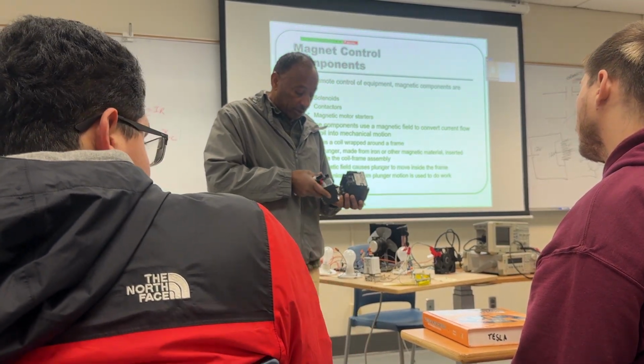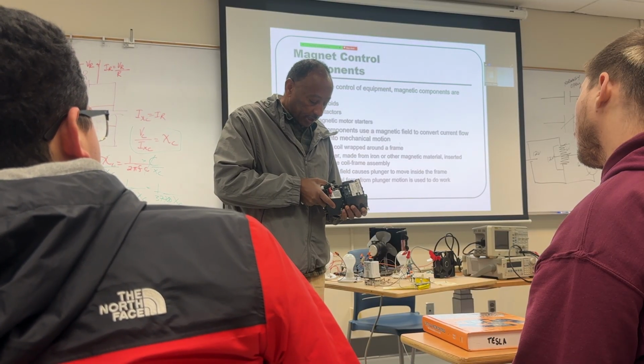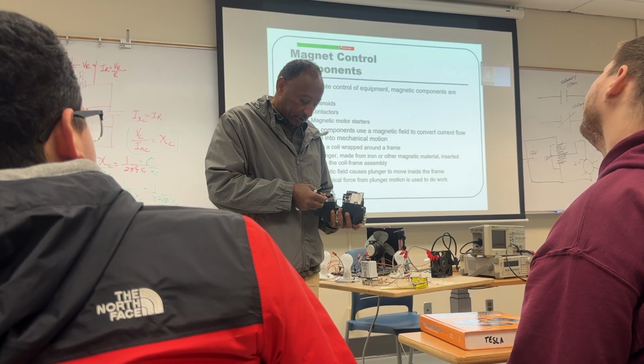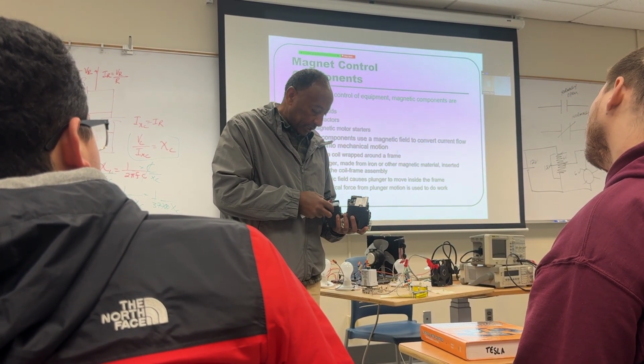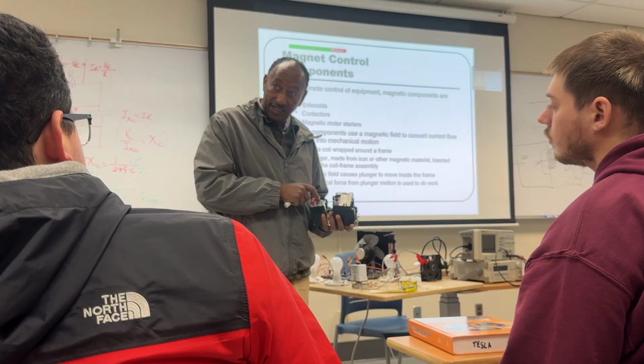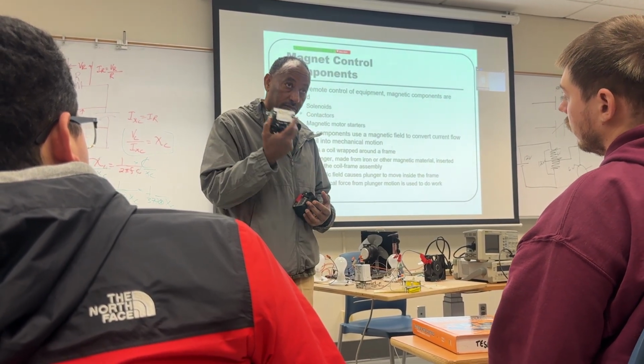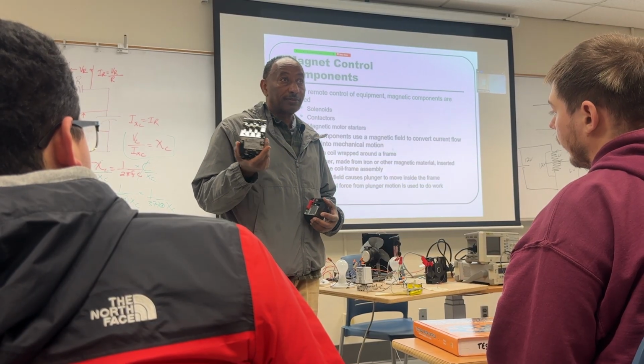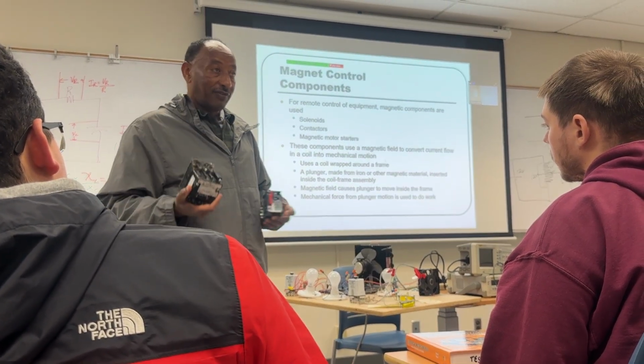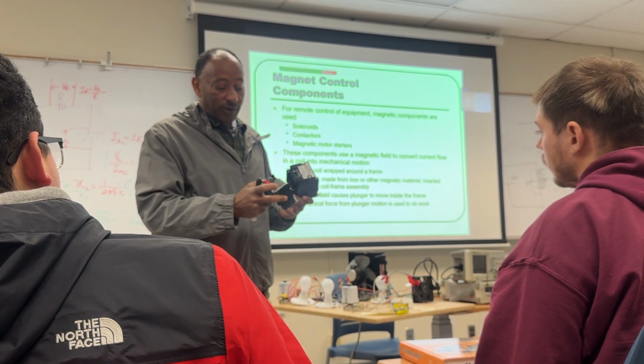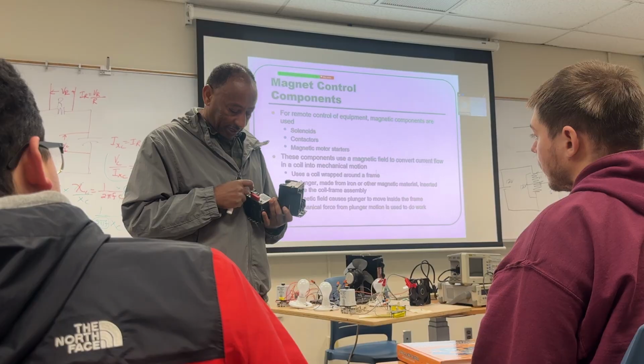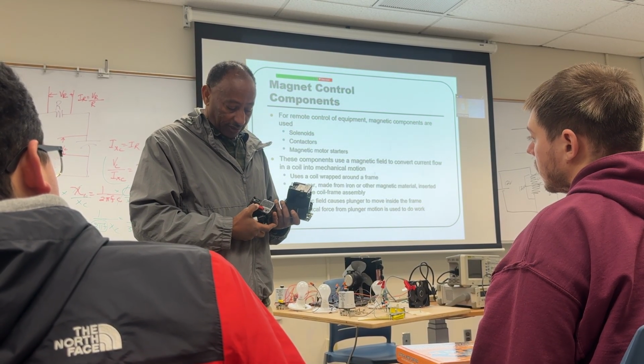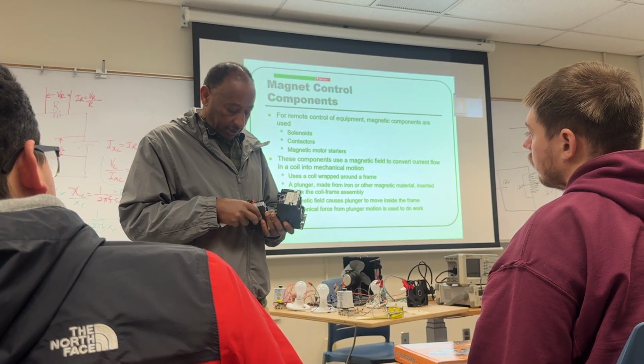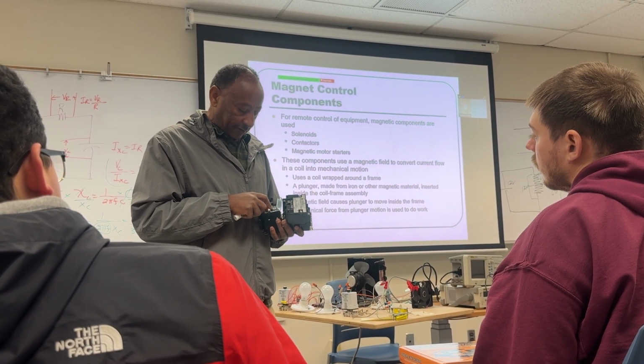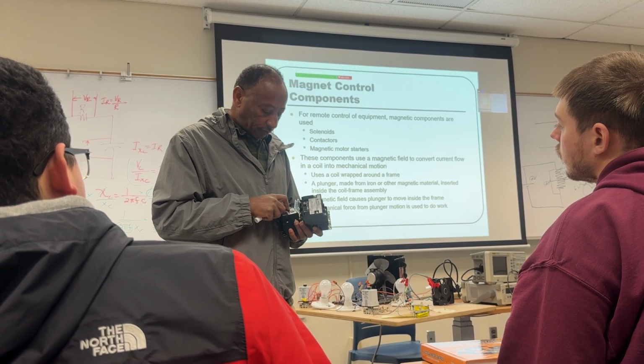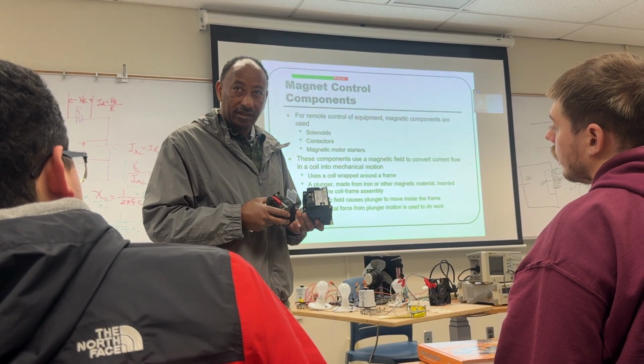In addition to that, it also has other features. This is overcurrent protection. It's a circuit breaker? This is also overload protection. If I'm using a heater or something other than a motor, I just need this. But if I'm using a motor, I have to add this because this has overload control. 95 and 96, that's overload. You can also reset the overload by doing this. The minimum current is 6 amps, and it goes up to 18 amps basically. Control up to 18 amps of current.